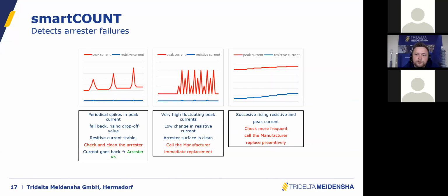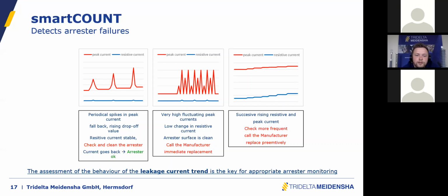And we have the third case of the zinc oxide degradation, which is, let's say, a slow process where you have to look for the trend of the resistive current and maybe check more frequently and ask the manufacturer if it's maybe all right, or if there is something bad happening to the surge arrester, or simply replace the surge arrester preemptively. What I clearly want to point out, all those failure modes are only detectable if you have a leakage current trend.